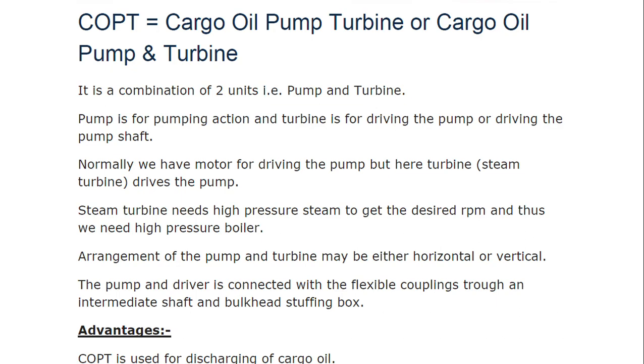When we talk about Cargo Oil Pump Turbine, it is a combination of two units: the pump and the turbine. Basically, it is a centrifugal pump, so all the parts of a centrifugal pump will be found here as well. The pump is for pumping action and the turbine is for driving the pump shaft. Normally we have a motor for driving the pump, but here we have a turbine — that is what makes it different.